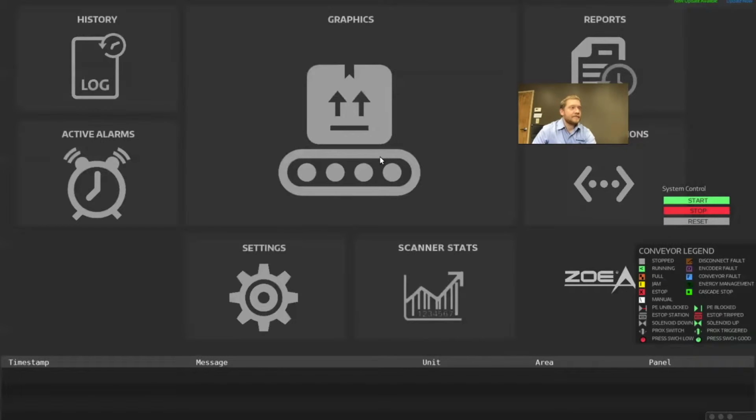And I'm guessing that's all alarm history. Yeah, instead of just a short one. Correct. And typically, for the system log and the alarm history and any database table that's being continually added to, we have a timestamp, obviously, and that information is usually housed for 30 days. And then we have a cleanup script that just deletes that information.